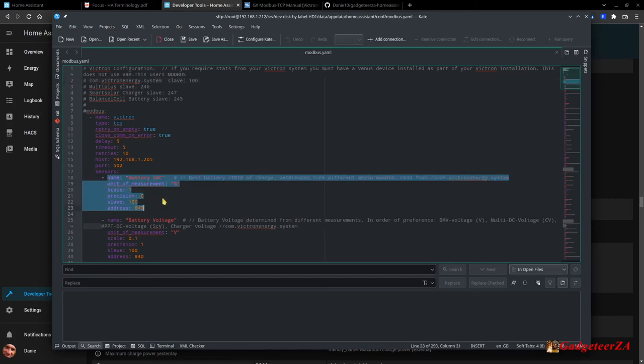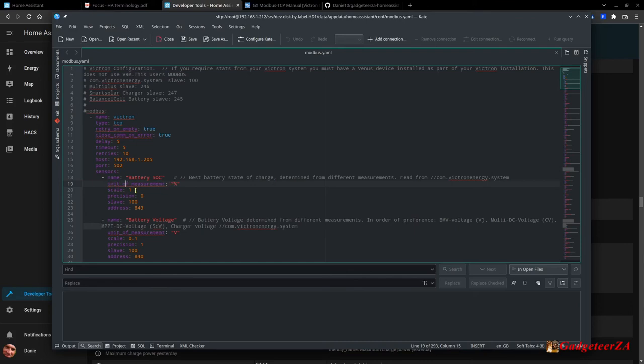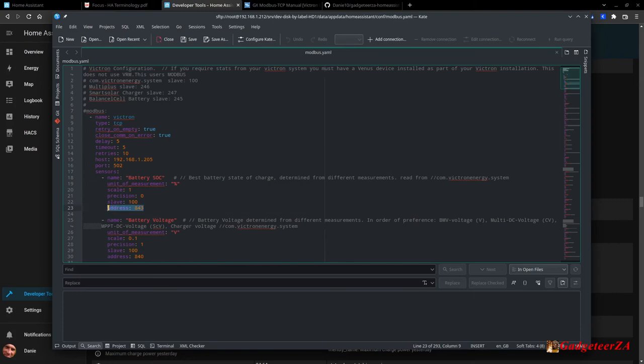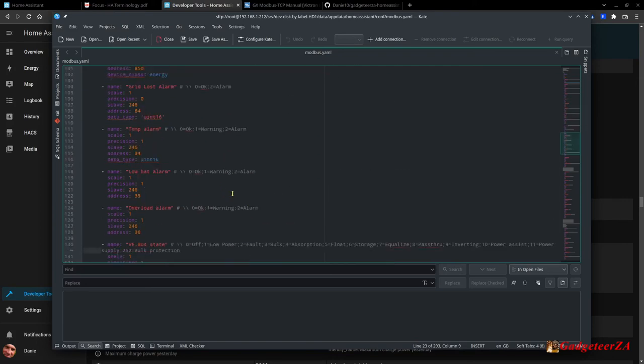When reading or writing a register, you specify the slave ID — say 100 — and then the register address. Each register holds something different: voltage, temperature, amp-hours, kilowatt-hours. For example a sensor named 'battery_soc': unit is percentage, scale is 1:1, precision is 0 (integer). For something like battery voltage the scale is 0.1 — device 246, address 34. You need to figure out the correct address register for each value.